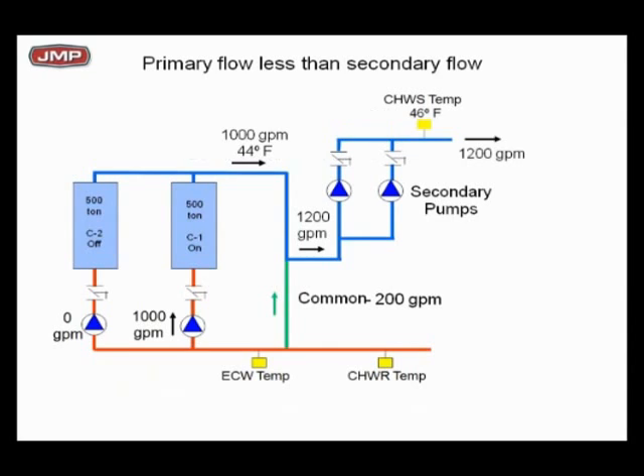And what kind of water is that going to be? Let's just see, let's put all the numbers. I think you understand this is going to have to be hot return water. We might have a problem here. Let's just see what happens. Suppose I take the 1200 GPM out, it's going to be 46. Now I bring back 1200 GPM to 56. I'm seeing a 10 degree delta T.